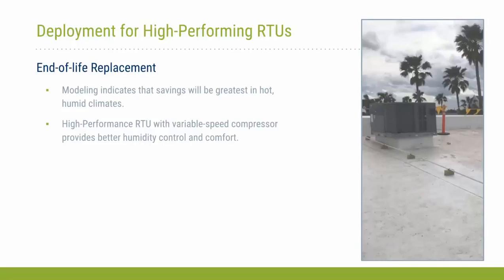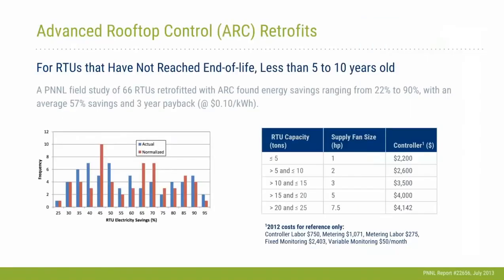If your unit is not at the end of its life, there's another solution called the advanced rooftop controller. So let's say your unit is 5 or 10 years old—this controller is an option where a variable speed drive is installed on the supply fan motor, and a controller is also installed to manage the economizer and ventilation operations more efficiently.